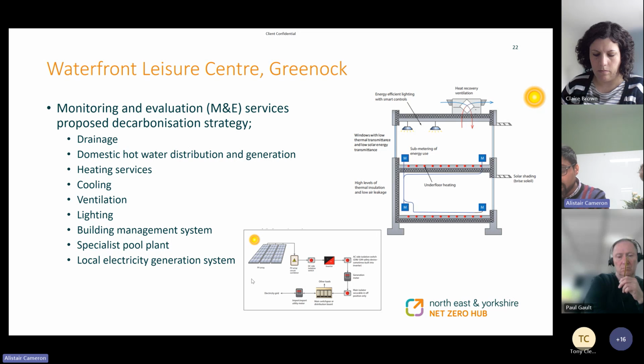And one of the immediate things we thought was, at the moment, the cooling is water to air chillers. So all the heat rejection just goes straight to atmosphere. And what we felt was this building is a building that has quite a significant cooling load throughout the year, and also quite a significant heating load throughout the year. So there's an opportunity there for heat to be transferred from the chiller to the heating circuit, whilst at the moment it's just getting rejected to atmosphere.